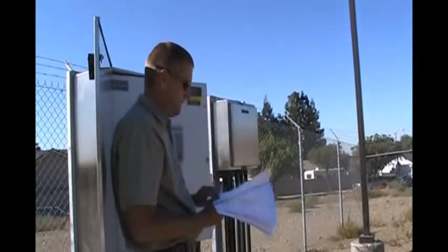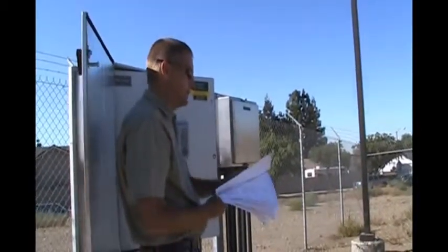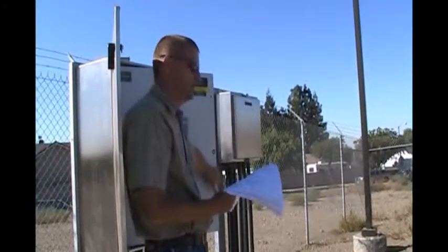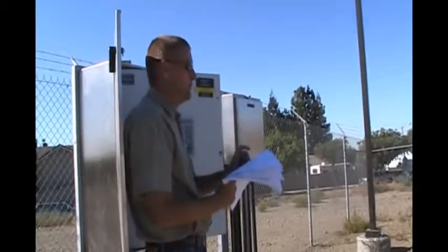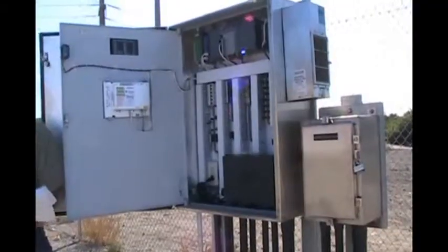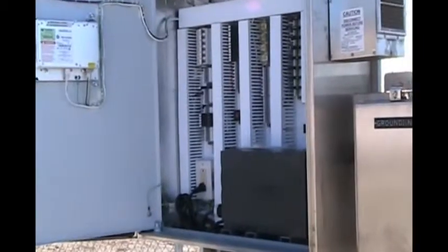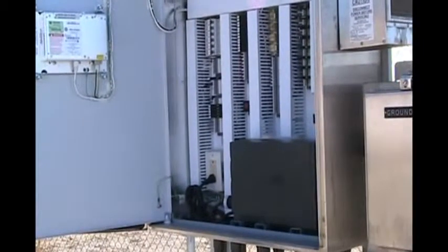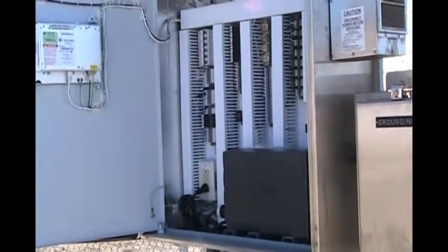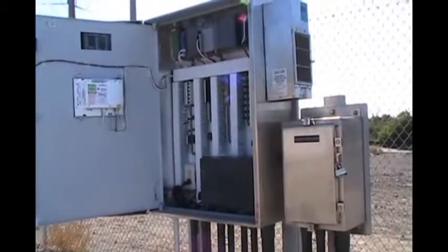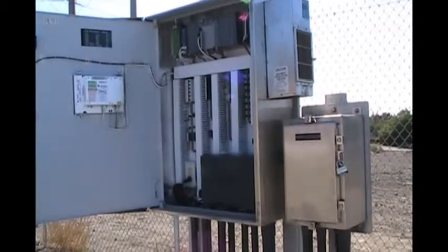Then there's a UPS on the right-hand side, and the receptacle is also on the utility power. From there, the UPS will be connected to the receptacle in here, bottom left. And from there, we're going to go to our control power. So we'll have our power supply, and we'll have our cards powered from the UPS. So you have, I think it was 30 minutes. If you lose power, you'll receive a signal that you lost power back at SCADA. You'll get all the signals that something's going wrong, and it'll run for 30 minutes. So somebody's going to run up here and fix it.